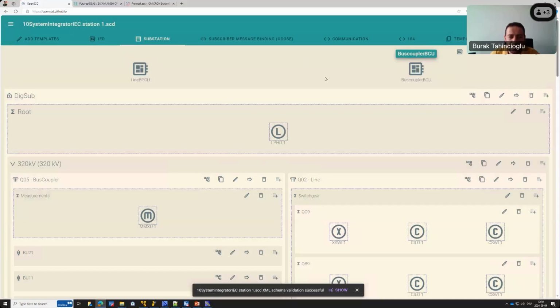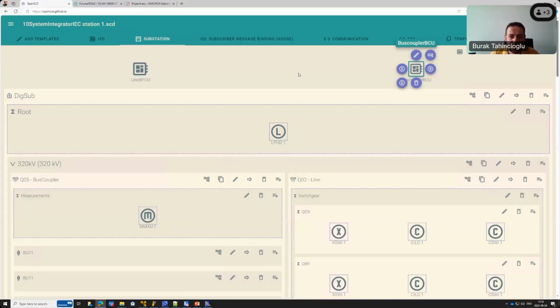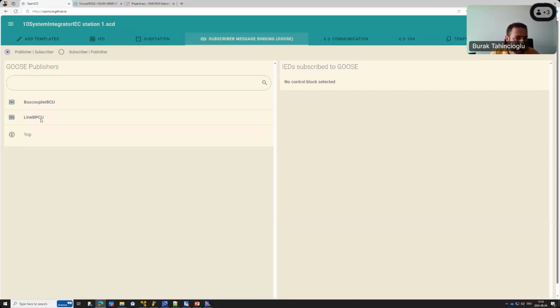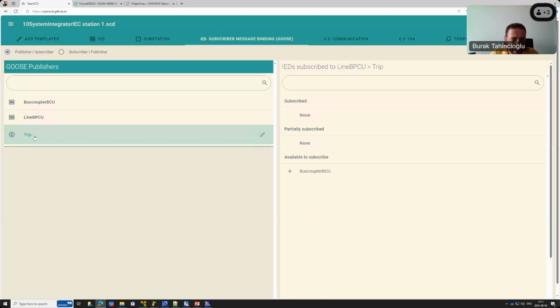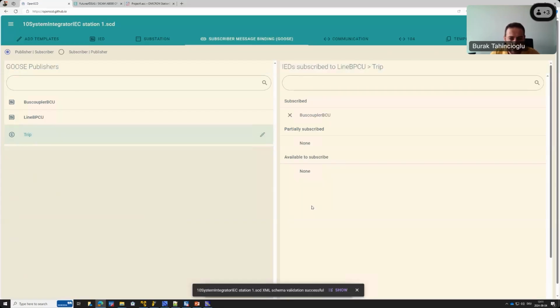Now we have one GOOSE. That's the GOOSE for trip. And then we want to subscribe to this GOOSE. Okay, how do we do this? It's quite easy. Let's do it here. I can now click on subscriber binding, and I see a trip GOOSE is available to subscribe by bus coupler, and with one click, it's done. Now I have subscribed to this GOOSE message.